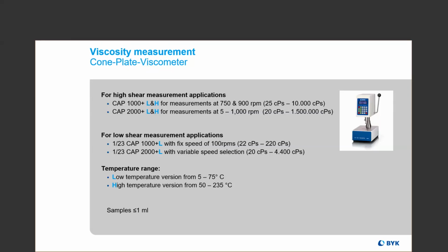Another benefit of these cone and plate viscometers is that they require very, very little volume of liquid in order to measure, less than 1 milliliter.